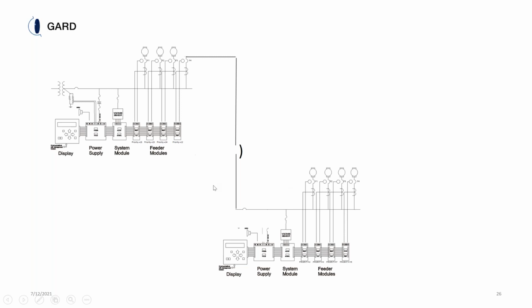So two things are going to happen here. This system is going to tell you that you have a fault on feeder number 4, and this system will tell you you have a fault in feeder number 3, because the fault is down here. So the fault is only in the path of the faulted circuit, and only the faulted circuit would indicate where the fault is. So it's basically telling you where the fault is, and all we have to do is follow it.